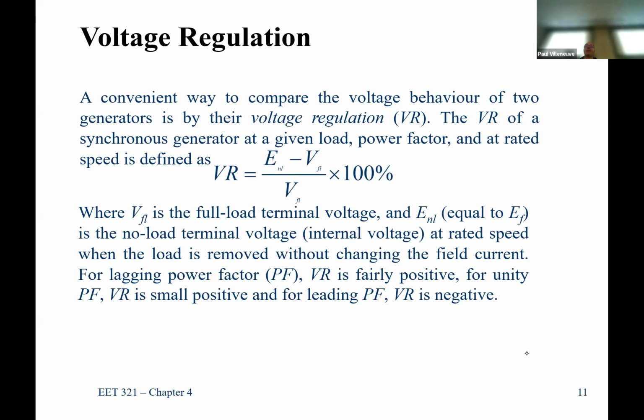So voltage regulation, same exact equation. Depending on how tight you want to maintain your tolerance, you're going to look at voltage regulation. Keep in mind that voltage regulation is not typically a usable number unless you've got a lot of load. This is a way of telling you what the synchronous reactance of your generator is. And those, if you remember from here, let's see, where's the, close it.